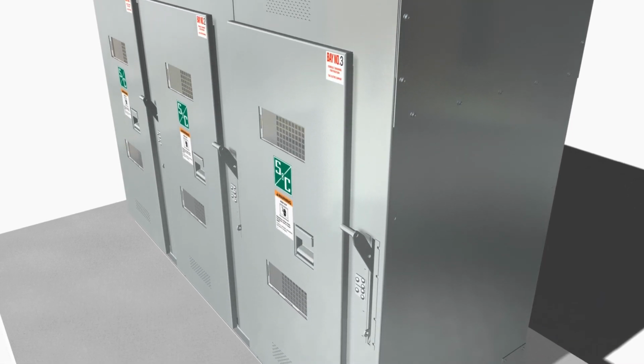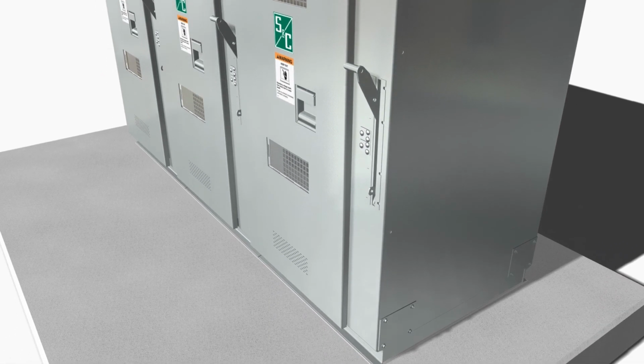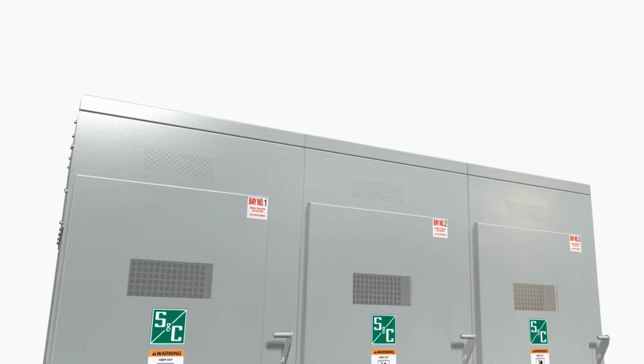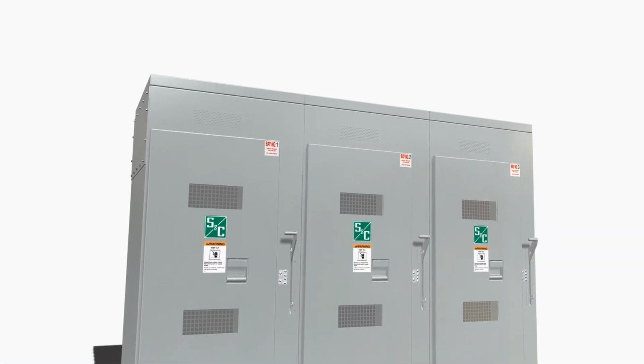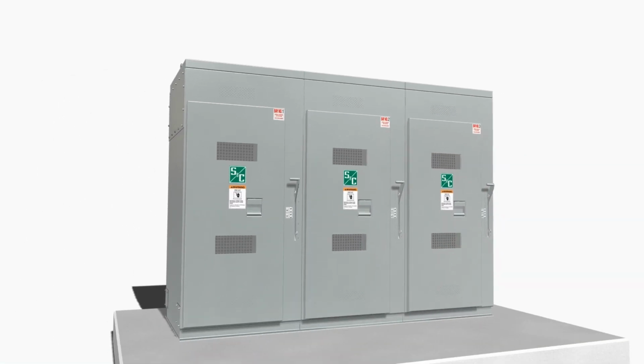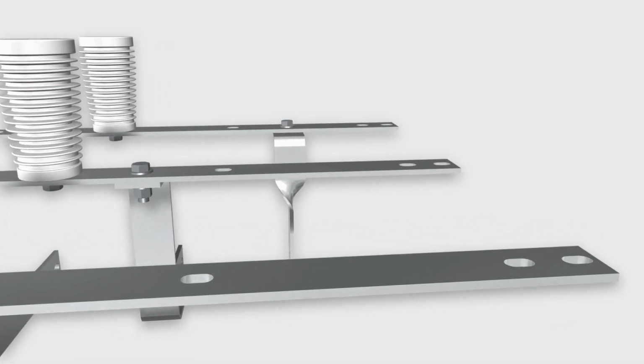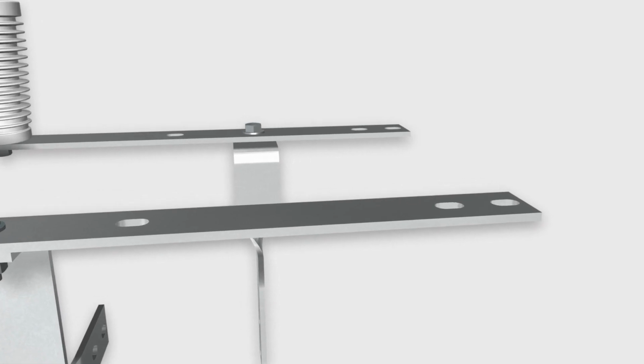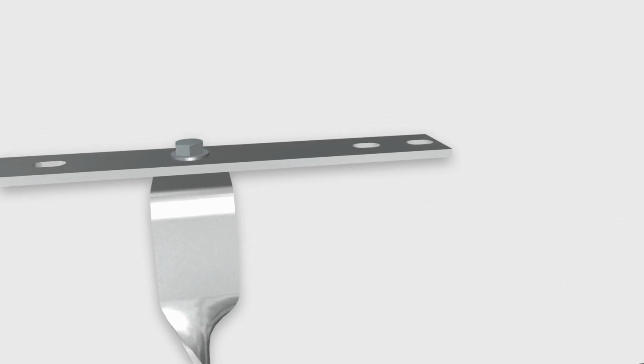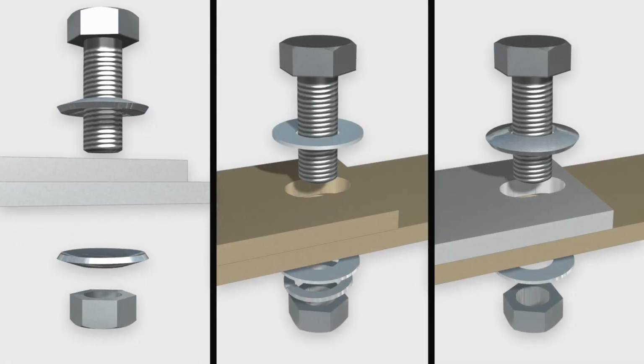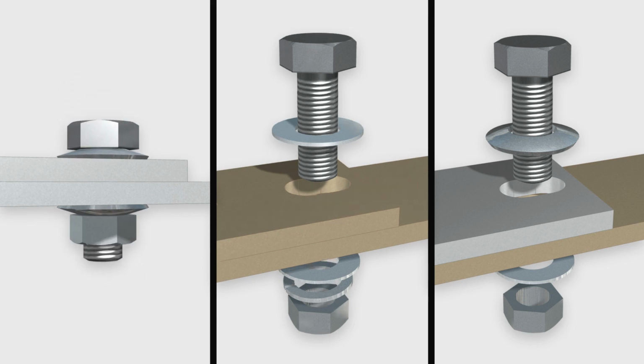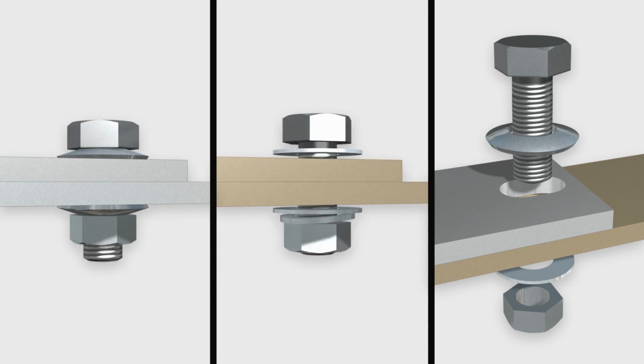Steps 8 and 9. The bus construction in S&C custom metal-enclosed switchgear is normally either aluminum or copper. Terminal pads on components may be aluminum, copper, or copper alloy. See the written instructions for information on how to connect different material types.